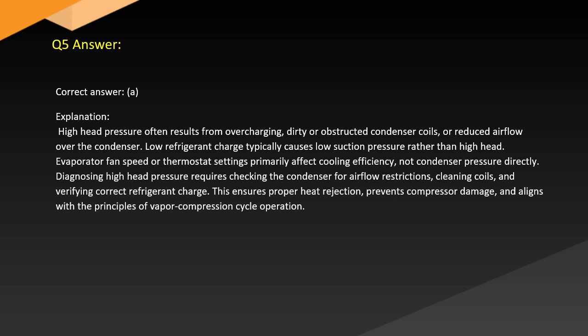High head pressure often results from overcharging, dirty or obstructed condenser coils, or reduced airflow over the condenser. Low refrigerant charge typically causes low suction pressure rather than high head. Evaporator fan speed or thermostat settings primarily affect cooling efficiency, not condenser pressure directly. Diagnosing high head pressure requires checking the condenser for airflow restrictions, cleaning coils, and verifying correct refrigerant charge. This ensures proper heat rejection, prevents compressor damage, and aligns with the principles of vapor compression cycle operation.